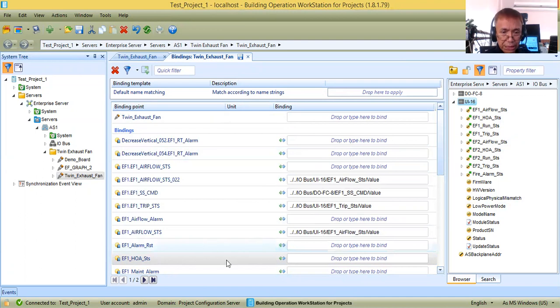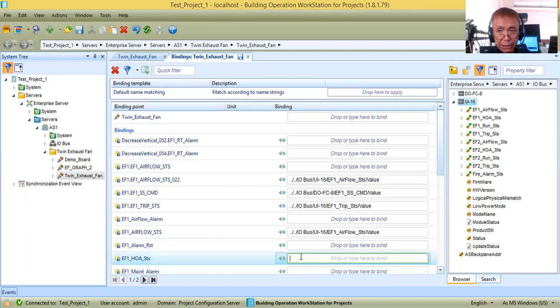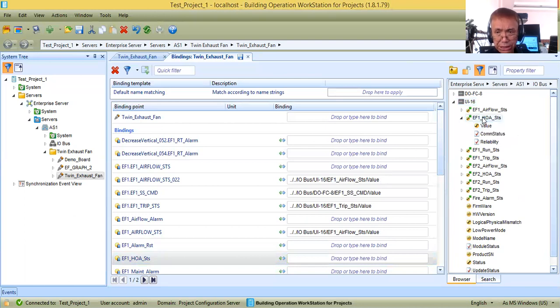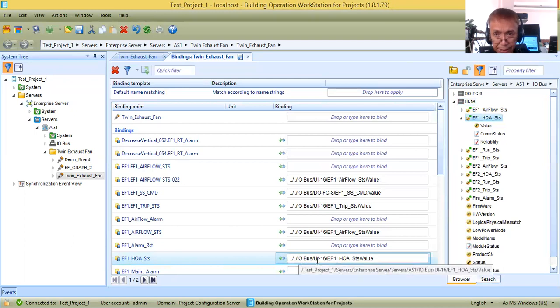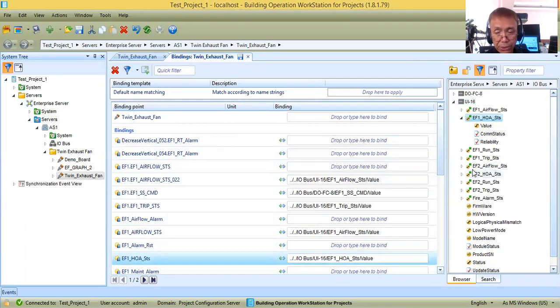When you bind a point, you are telling the BMS graphics where to get or fetch the value. For EF1 HOA status, I go to the IO module and find the EF1 HOA status point. By default there is only one value available, so you click and drag it to the respective point. This means EF1 HOA status will get its value from the IO bus — UI16, point EF1-HOA-Sts.